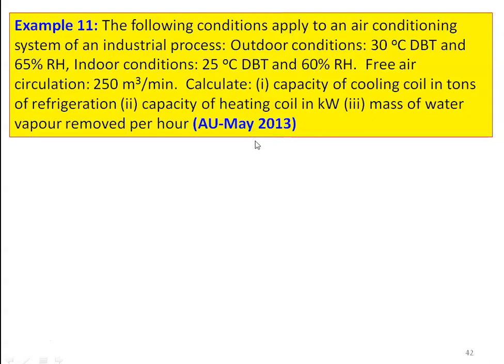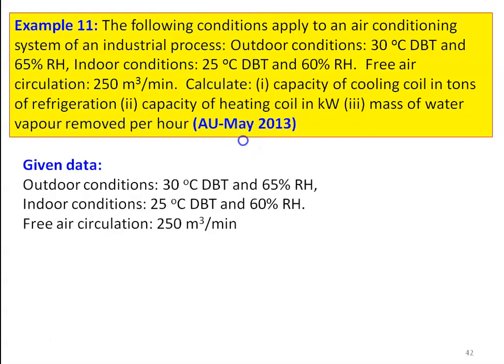Example number 11: The following conditions apply to an air conditioning system of an industrial process. Outdoor conditions are 30°C dry bulb temperature and 65% relative humidity. Indoor conditions are 25°C dry bulb temperature and 60% relative humidity. Free air circulation is 250 m³ per minute. Calculate: capacity of the cooling coil in tons of refrigeration, capacity of the heating coil in kilowatts, and mass of water vapor removed per hour.